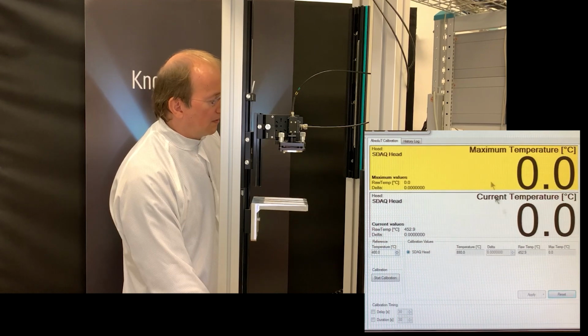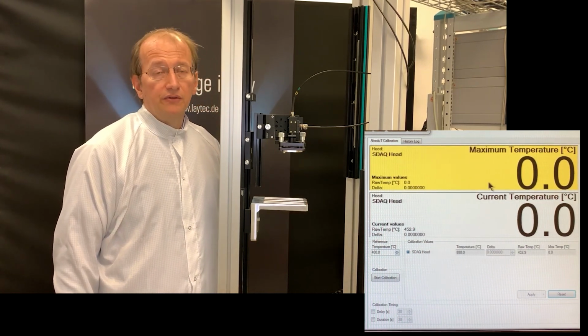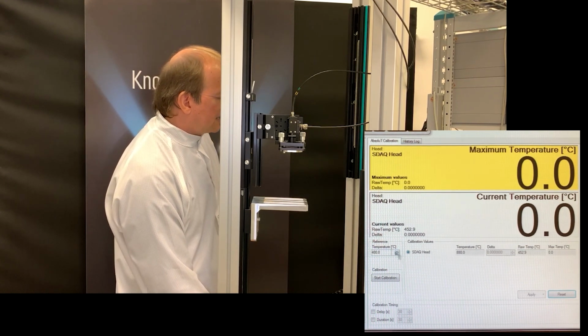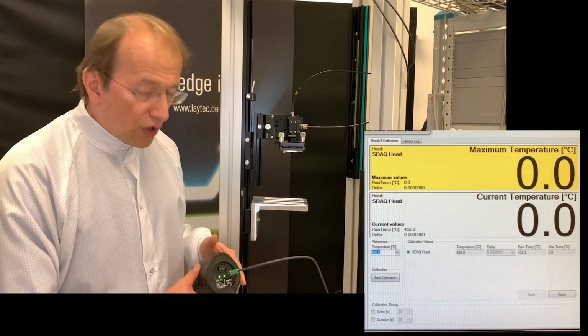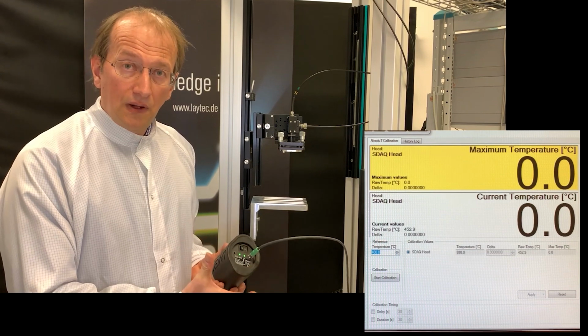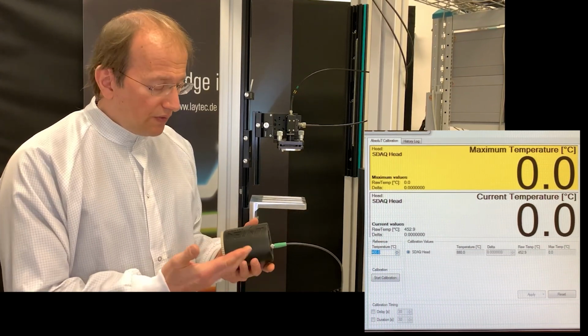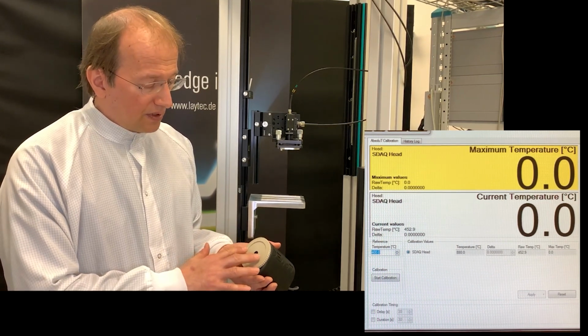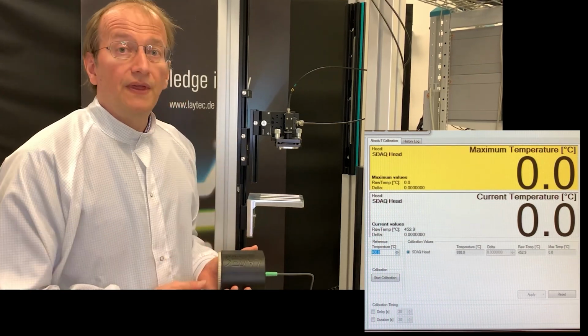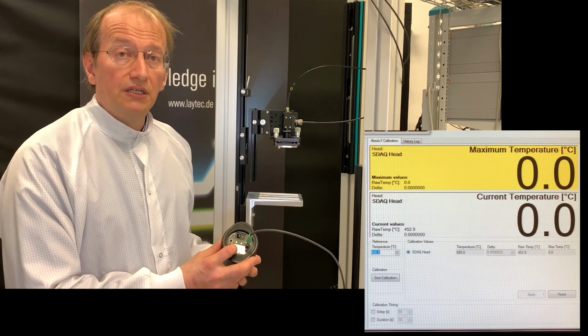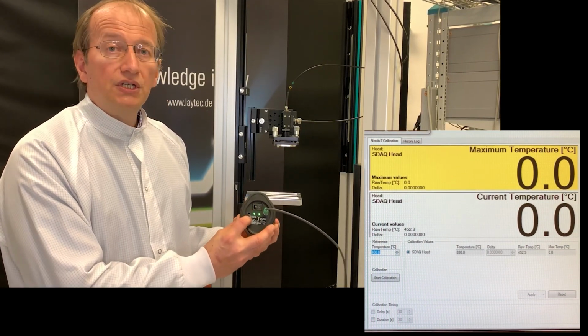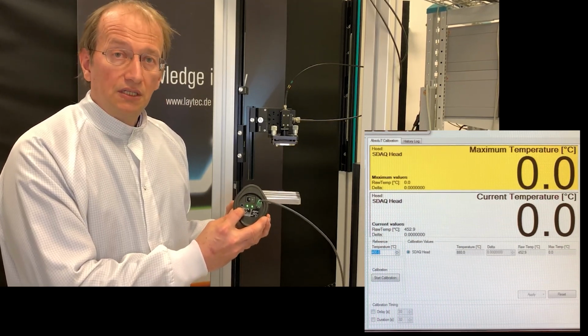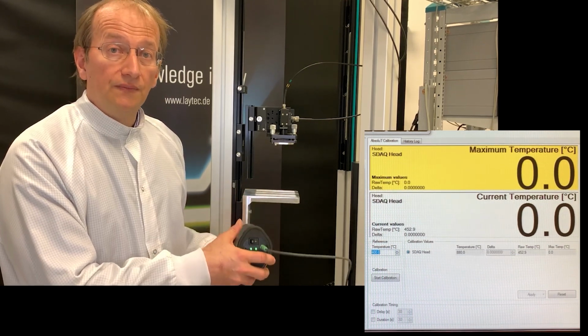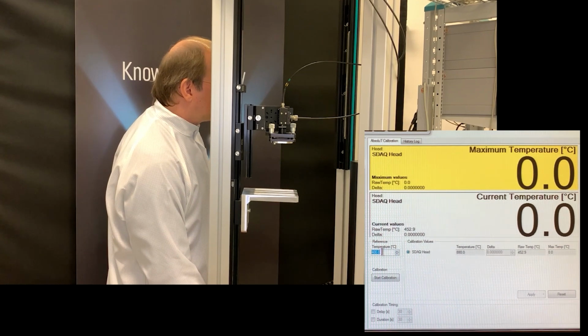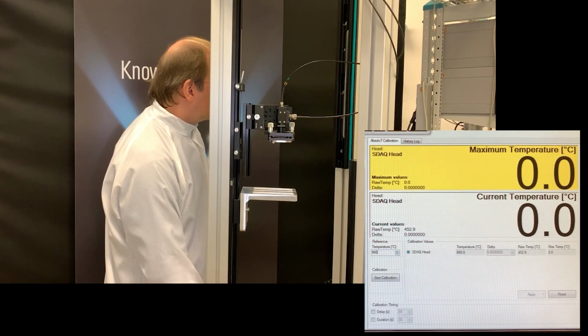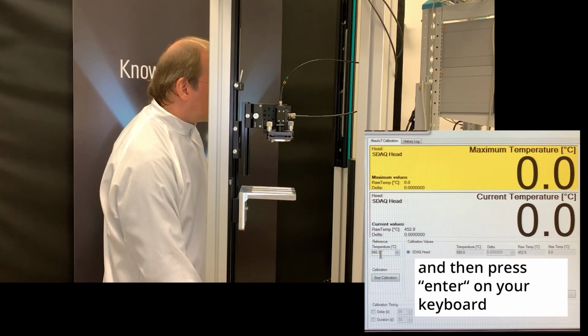So it looks like this. It might be when you start up the first time that you see numbers from the previous recording, just quickly press the reset button. Next step is very important. Each of the AbsoluT devices have individual referenced, calibrated temperature, which our AbsoluT tool is simulating. It's creating a fraction of a spectrum which matches with our pyrometer. And that is calibrated on our side with a calibrated pyrometer. And the temperature, this specific AbsoluT, so you have to, each AbsoluT has an individual value, is in our case 900.3 centigrade. And this we have to type in reference temperature.